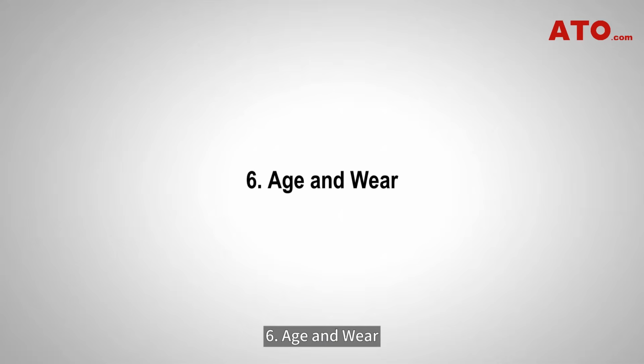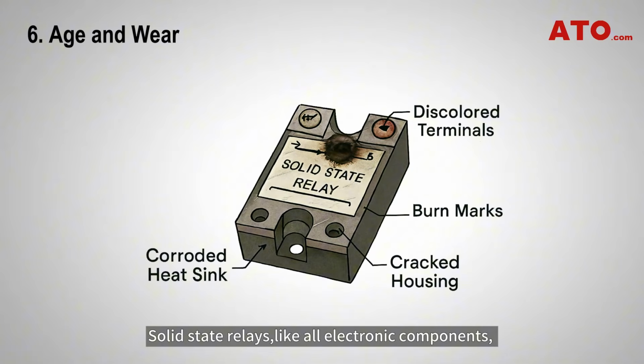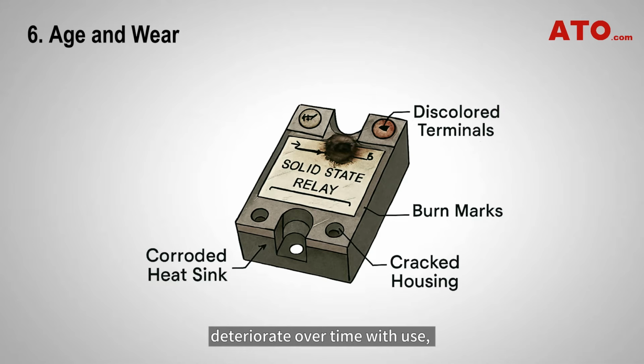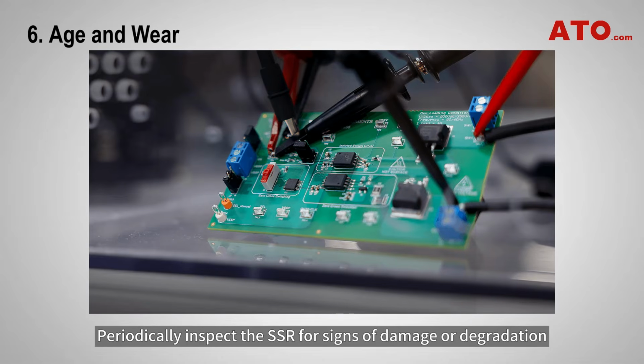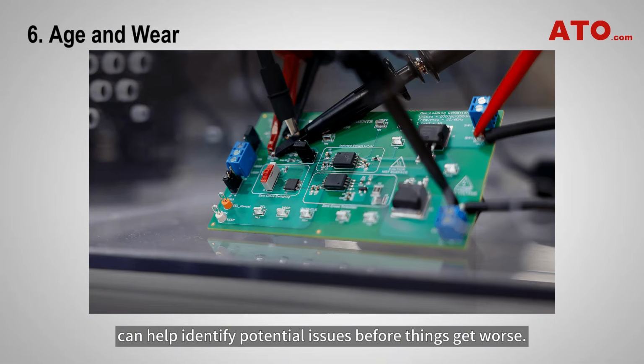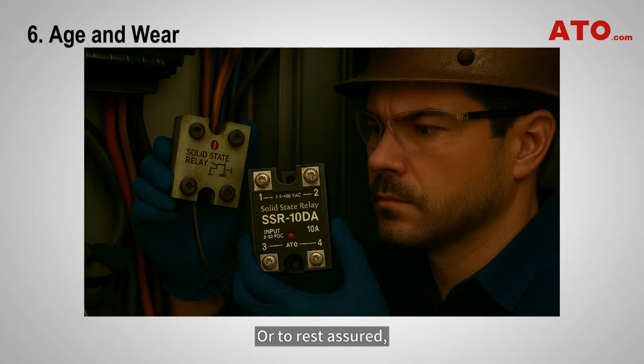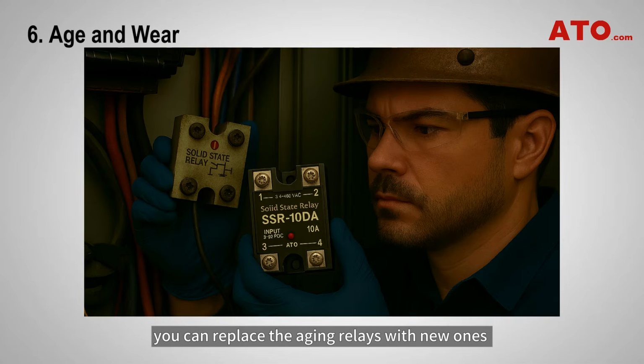Number 6. Age and wear. Solid-state relays, like all electronic components, deteriorate over time with use, increasing the likelihood of failures. Periodically inspecting the SSR for signs of damage or degradation can help identify potential issues before things get worse. Or to rest assured, you can replace the aging relays with new ones so as to maintain system reliability and performance.